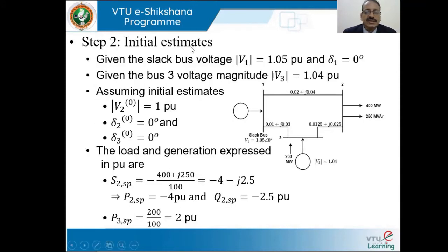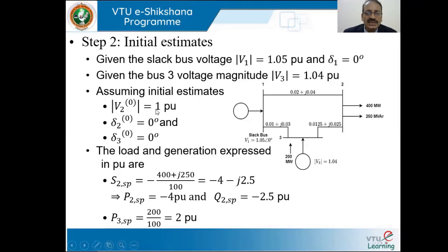For the initial estimates: the slack bus voltage magnitude is 1.05 at angle 0. For bus 3, voltage magnitude V3 = 1.04 per unit is specified. Since the bus 2 voltage is not given, we assume a flat start: V2⁰ = 1 per unit. For bus 3, the angle is not given, so we assume δ3⁰ = 0 degrees.